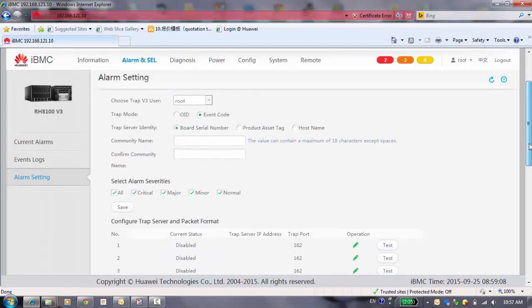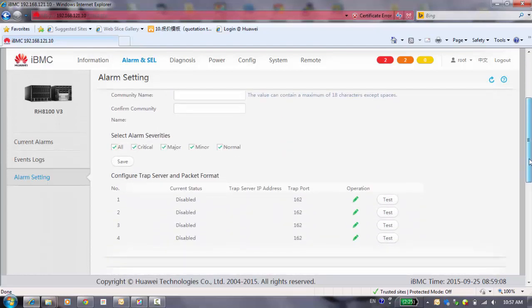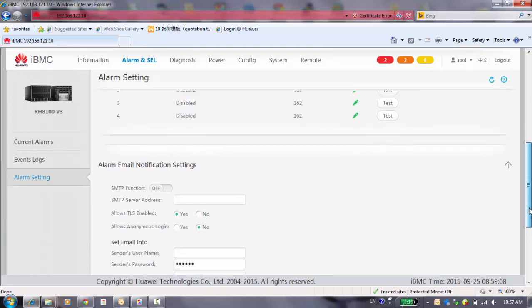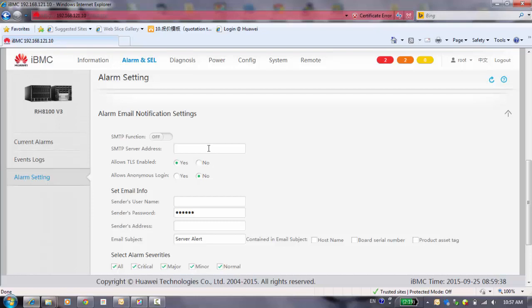Alarm setting. Here you can choose how to check your alarm state. You can use the SNMP to check your alarm. You can set some port here. You can get an email about the system alarm, and you can monitor and control your system from the remote, even if you stay at home or out of office. You can set the SMTP server's address.